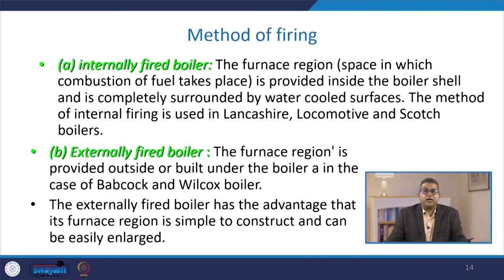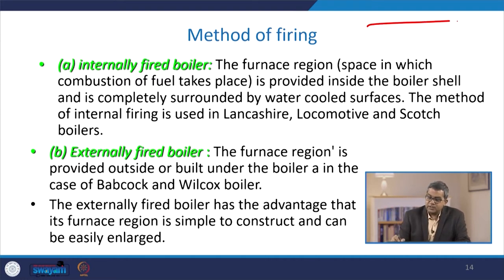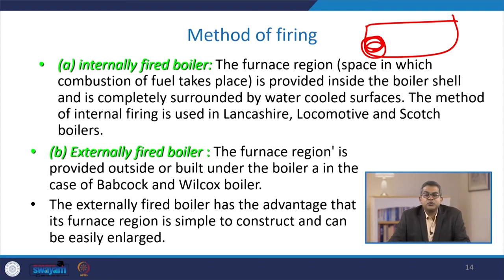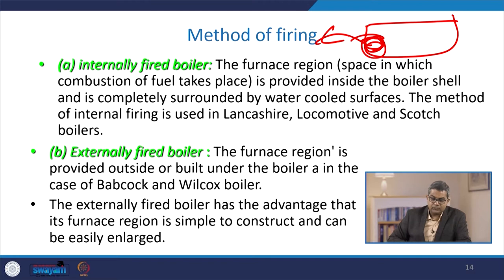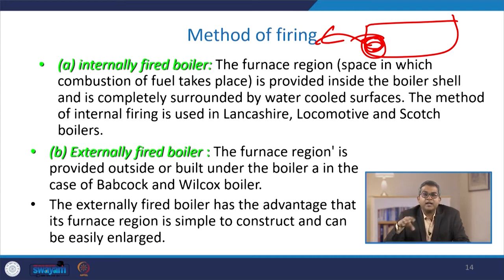In an internally fired boiler, the furnace region where combustion takes place is provided inside the boiler shell, completely surrounded by a water-cooled surface. Internal firing is used in Lancashire, locomotive, and Scotch type boilers. In externally fired boilers such as Babcock and Wilcox boilers, the furnace is outside or built under the boiler shell. The externally fired boiler has the advantage that its furnace region is simple to construct and can be easily enlarged based on capacity requirements.